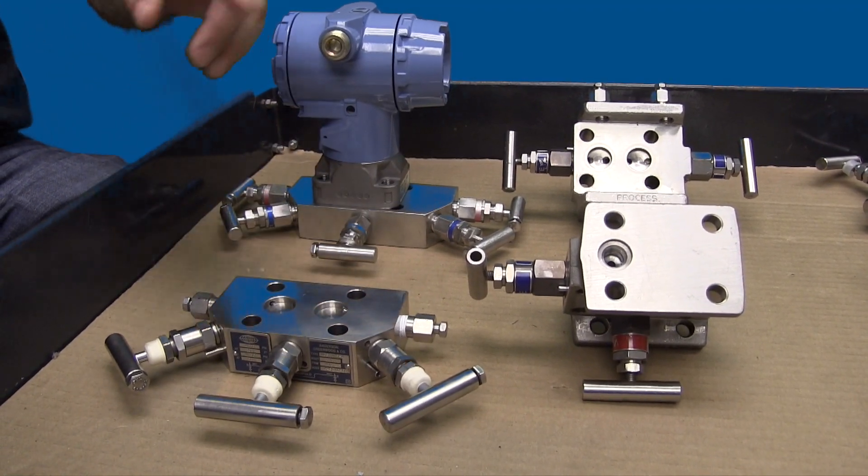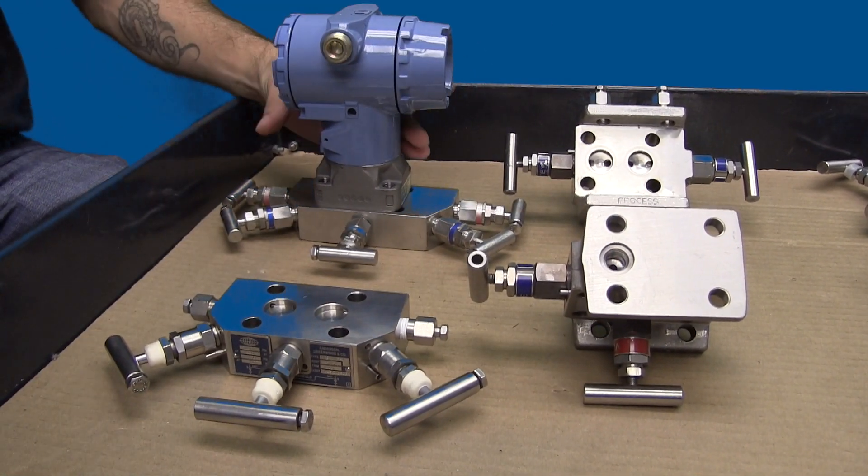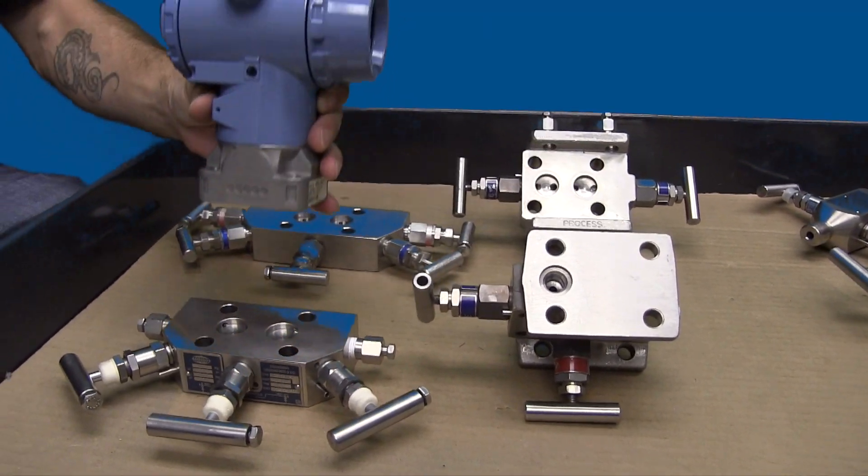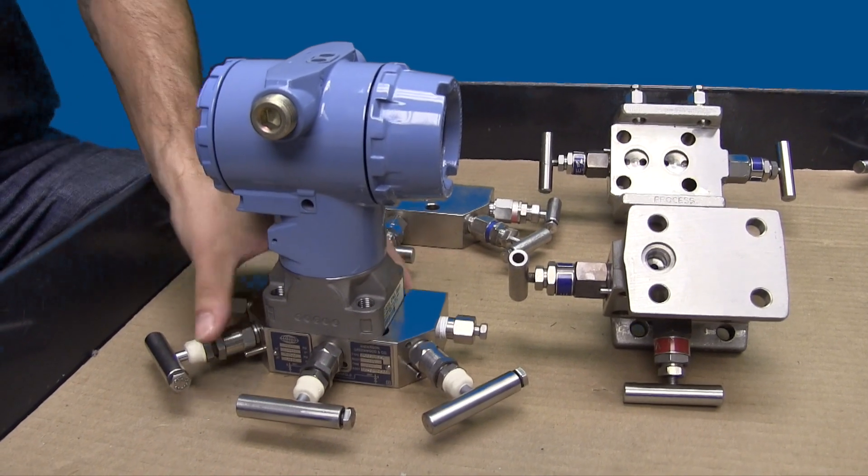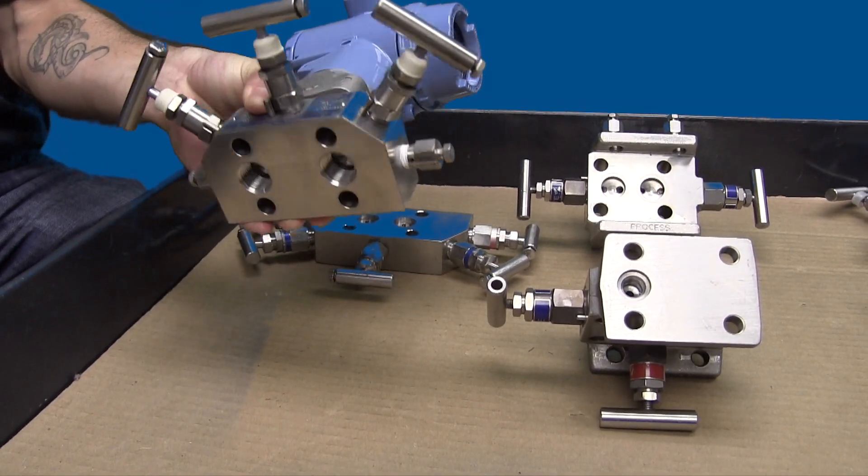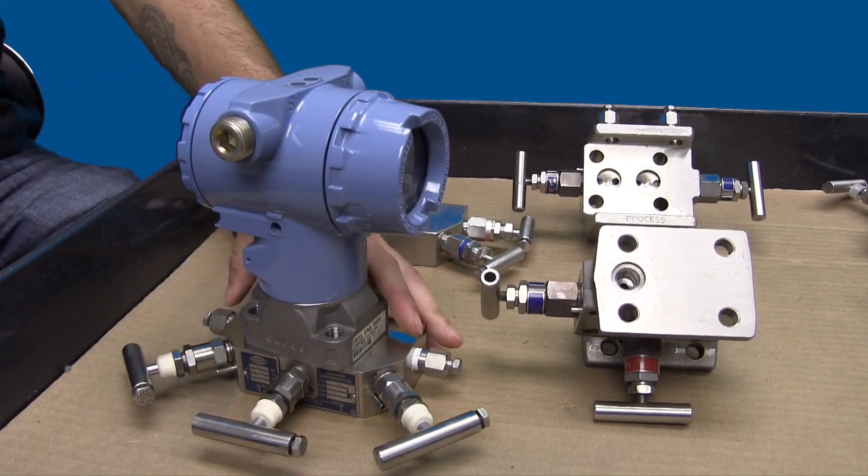Traditional manifolds have the process connection coming in from the side of the manifold. Alternatively, coplanar style manifolds have the process connection coming in from the bottom. These are both available in half-inch and quarter-inch process connection sizes.